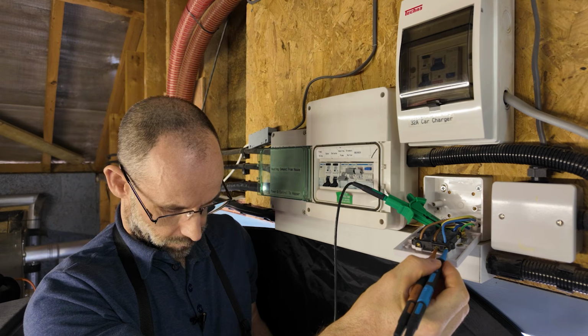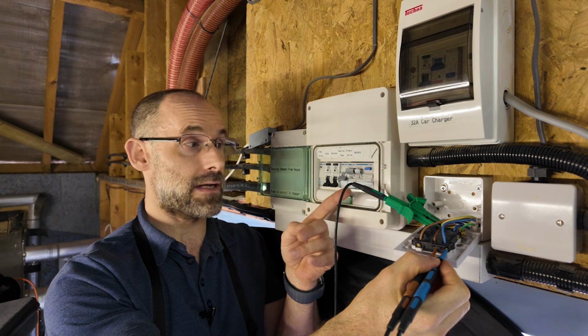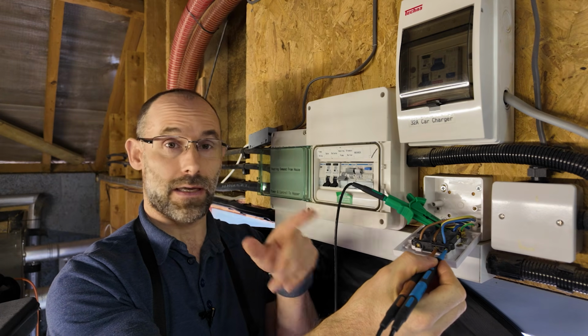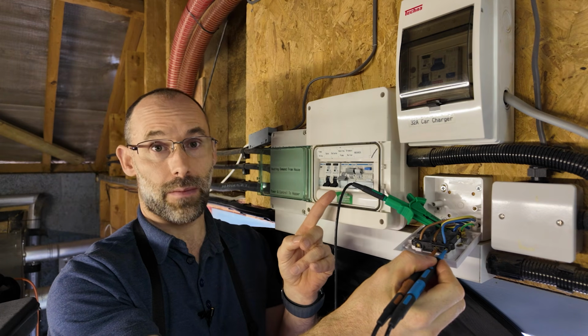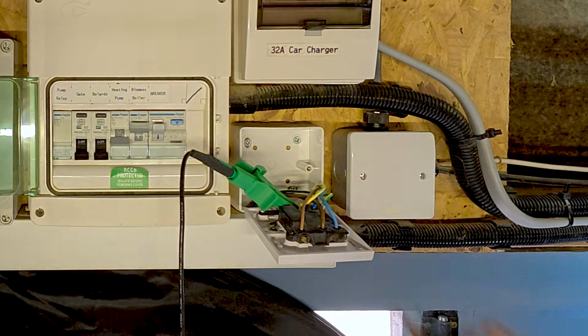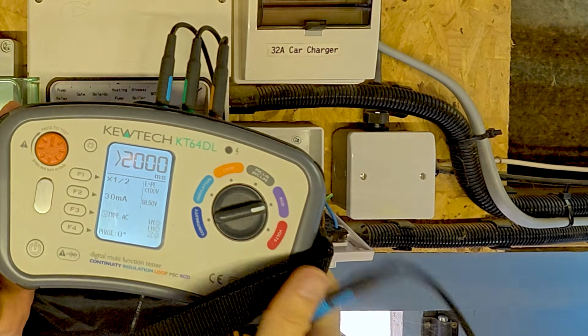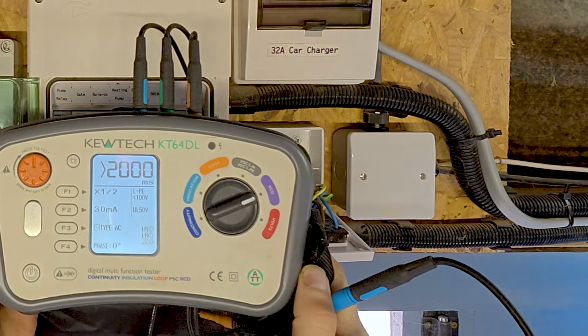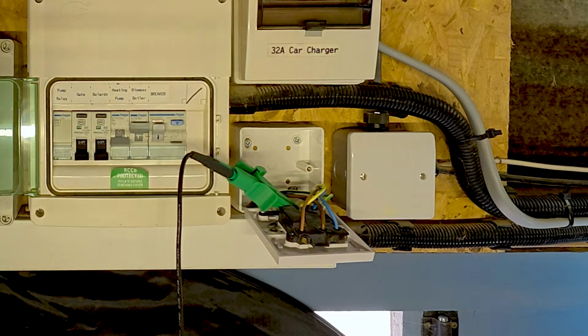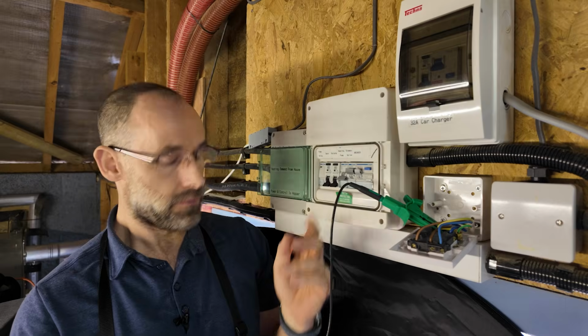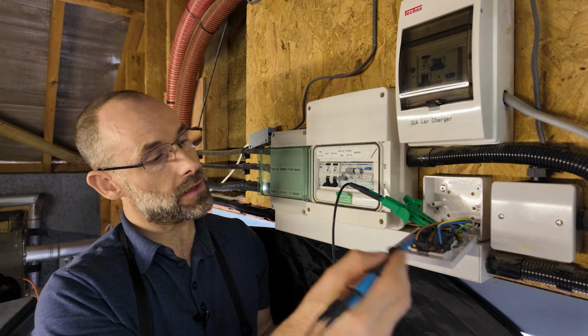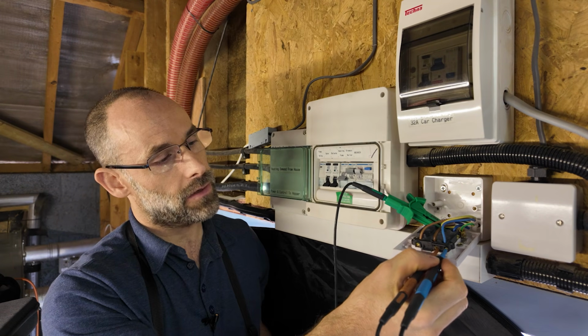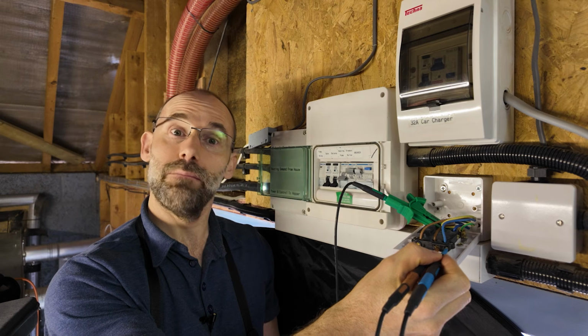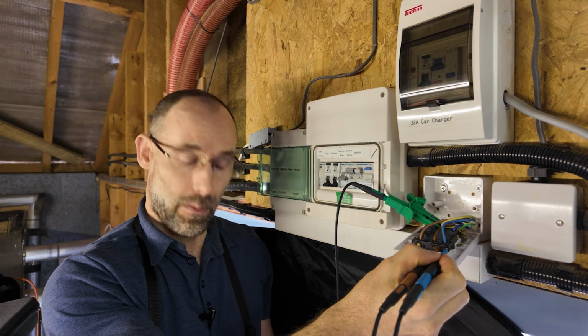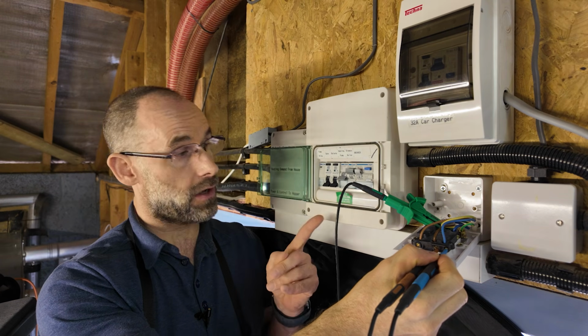Here what I'm testing for is putting half of the rated fault current through this circuit, and this should not trip. It checks for at least 2 seconds, and by the end we get something saying, I tested at half the current, 15 milliamps, for 2 seconds, and it didn't trip. Awesome. So now I tell my meter I'm going to test at a full 1 times. Now it's going to put 30 milliamps of fault current in here, and when it does so, we would expect this RCD to trip.